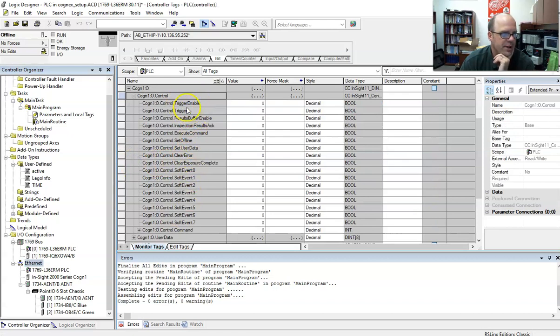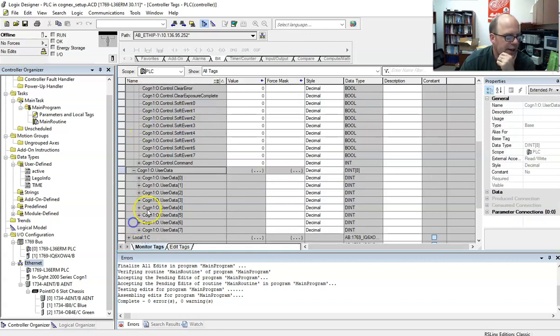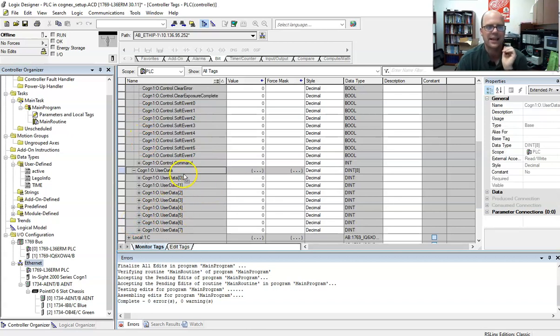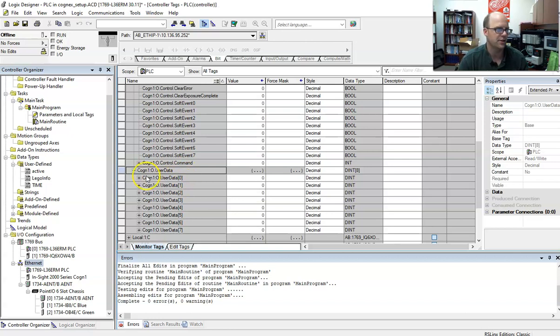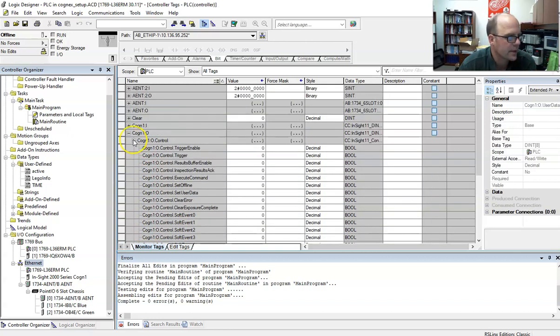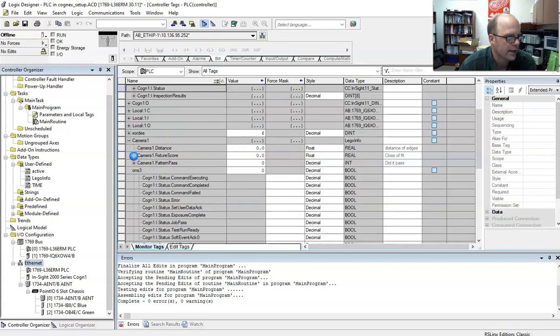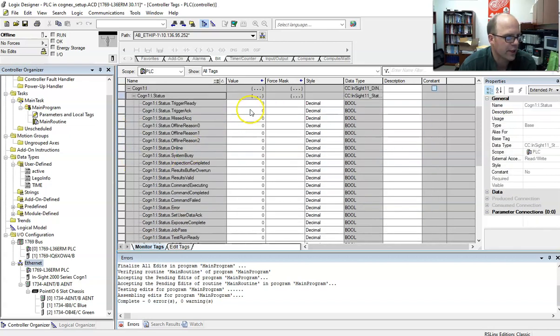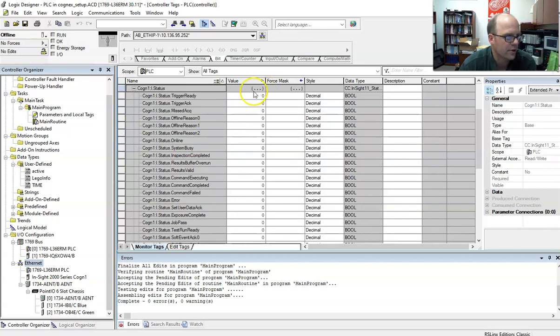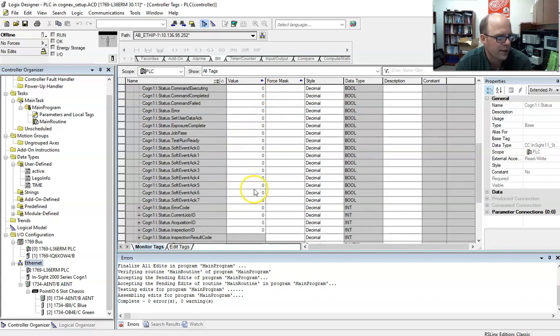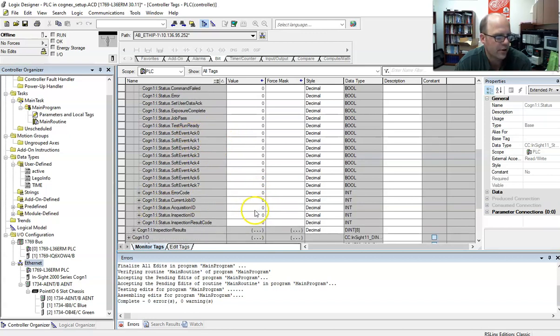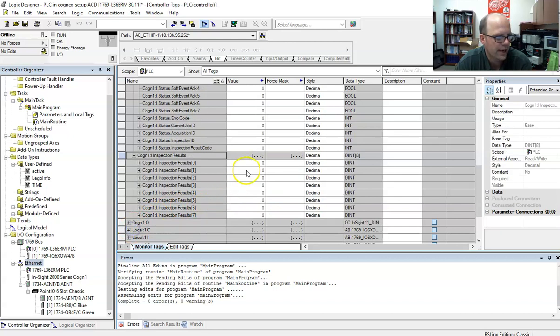Here, trigger, trigger enable, offline. Those are the ones that I'm going to use primarily because that's going to trigger the camera. You can set up user data which I'll walk through, but I'm not sending anything out to my camera yet. I'm just receiving stuff. Receiving stuff is a lot easier to set up. If I go into my inputs, that's stuff that I get from my camera. Again, statuses with the camera, so trigger acknowledge, you can set these up and do everything with the information you get from the camera, current ID, error code, et cetera.